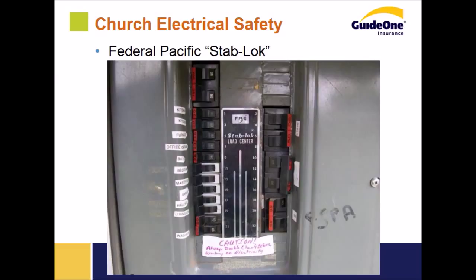The connections seem to fail, and the overheating that those loose connections caused severely damaged the breakers and caused them to not trip at all. It kind of welded those breakers in the on position. These were widely installed in the 60s, 70s, and 80s, so we've still got thousands of them out there. And we need you to tell us if you find Federal Pacific Stab-Lok breaker panels at our churches.